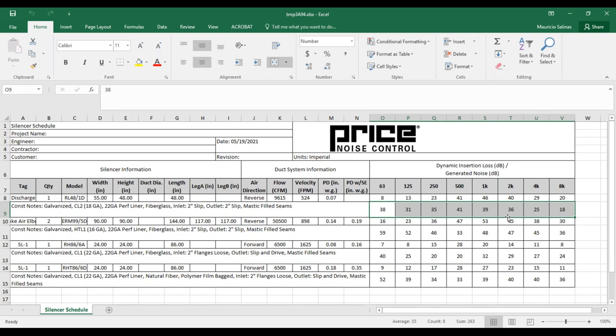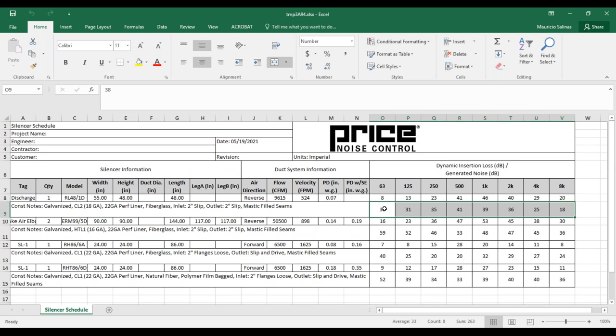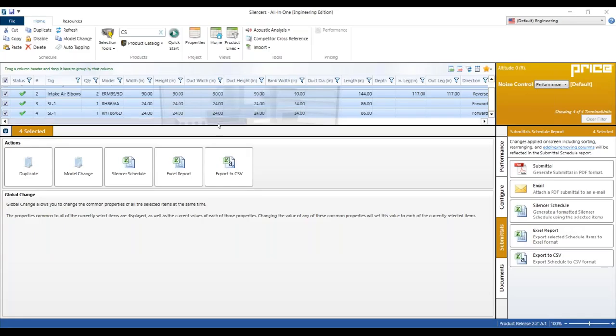And if you recall, and this is a test for those who were in yesterday's presentation, if the sound power levels are 10 decibels of difference between one another, so in the 63 hertz octave band, the fan has 96 decibels. If I add 96 decibels plus 38 decibels, am I adding any noise? It's a trick question. I'm going to check the chat. Well, the answer is no. When you add 96 plus 38, it's still going to be 96. So that's just kind of using the theory from the HVAC fundamentals that Chris presented yesterday. All right, so that's how easy it is to do silencer selections.